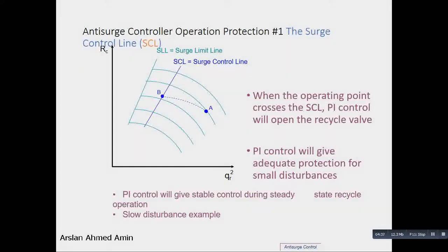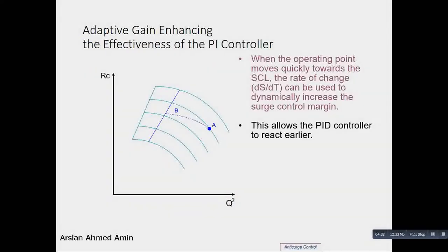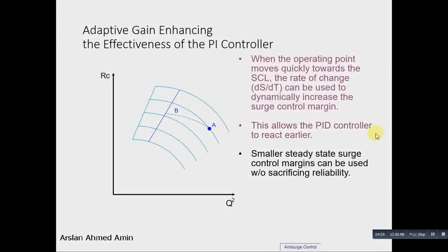But what if the surge comes very fast? When the operating point moves quickly towards the surge control line, the rate of change can be used to dynamically increase the surge control margin. This allows the PI controller to react earlier. Smaller static surge control margins can be used without sacrificing reliability.